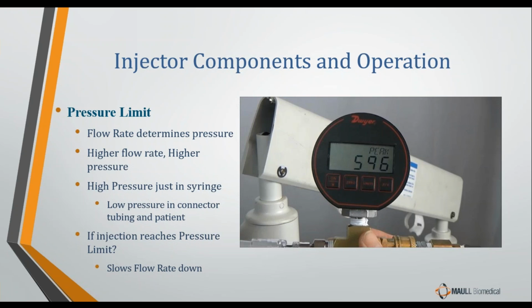Now what's going to happen is they have set that pressure limit too low. Now when we actually perform this injection, when we shoot this 5 milliliter per second injection, and we only limit the pressure inside the syringe to 200 psi, let's say, the injector will pressure limit. The injector will not actually inject at a rate of 5 milliliters per second. It will be injecting at a much, much slower rate. Everybody's expecting a rate of 5 milliliters per second. We're expecting a certain quantity of fluid into the patient during this procedure so that we see the blood vessels show up nice and clear on the actual X-ray image. But now my injector is shooting really, really slow. We're not getting nearly as much contrast in the region of interest as everybody's expecting.